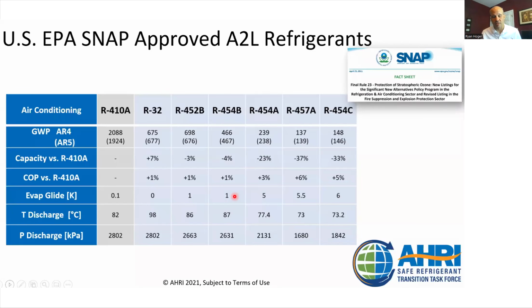And the concern, at least when we had 410A back in the day, even though it had a lower glide and everyone was freaking out about it, they freaked out about the higher pressure, right? And then they freaked out about the glide. And they were like, oh, dude, if there's a leak in the evaporator coil, we're not going to be able to fix the leak and then top it off. We're going to have to pull the charge out and recharge it from scratch. No one has ever done that with 410A ever. And no one's going to do that with 454B ever.